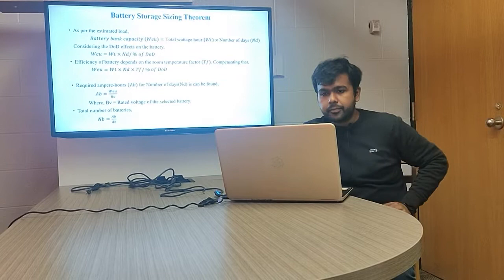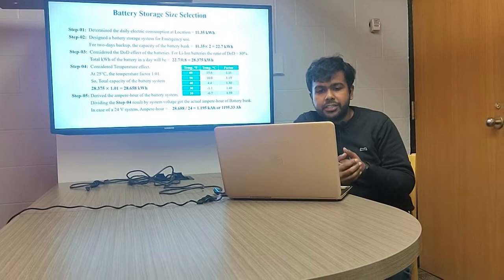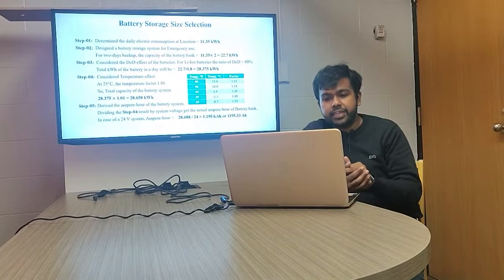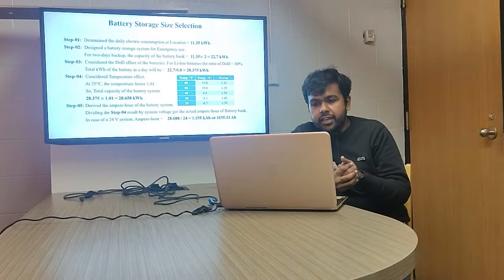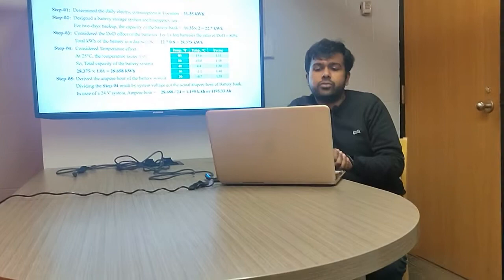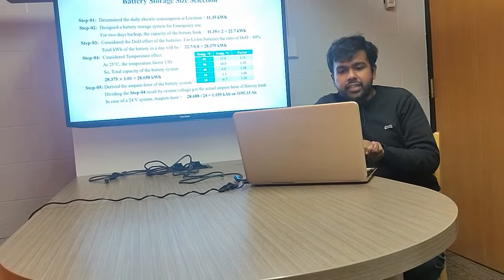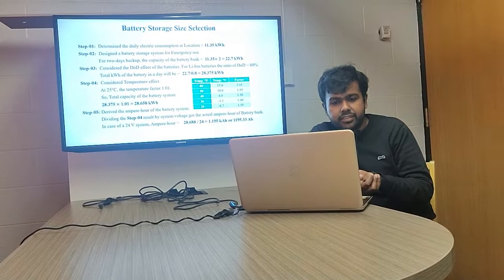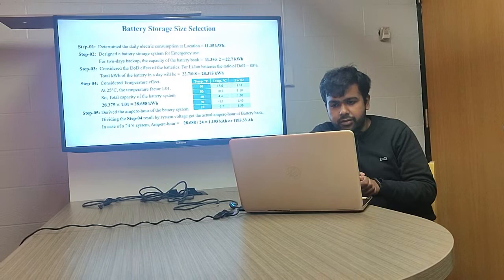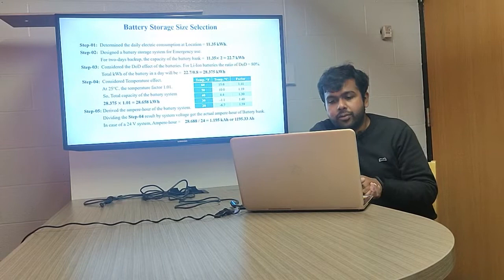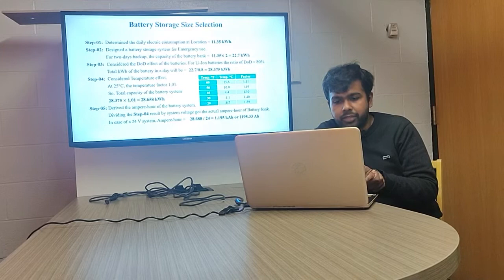In this slide, we divided the whole operation into five steps. In step one, we calculated the daily load consumption of 11.35 kilowatt-hours. For a two-day backup, we considered a total of 22.7 kilowatt-hours of load. In steps three and four, we considered the depth of discharge effect and temperature effect to measure the total watt-hours of the battery. On the right side, there is a chart showing the temperature factor for different temperatures.